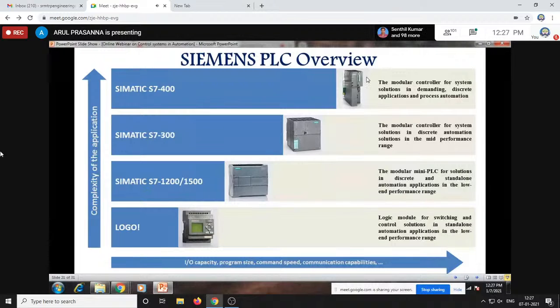S7 300 and 400 are PLCs meant for high-end processing. The variation between S7 300 and S7 1200 is this: the S7 1200 will be able to process up to a few hundred or 200 inputs and outputs. So the CPU has the capability of processing up to 100 or 200. If the available onboard terminals are 20, 24, or 32, additionally you can go for some 100 or 150 add-on units. But when compared to S7 300, a single CPU can process up to 1000 IOs. So think about the capability of the CPU. Where this can process up to 200, that one will have about 5 times more capability.